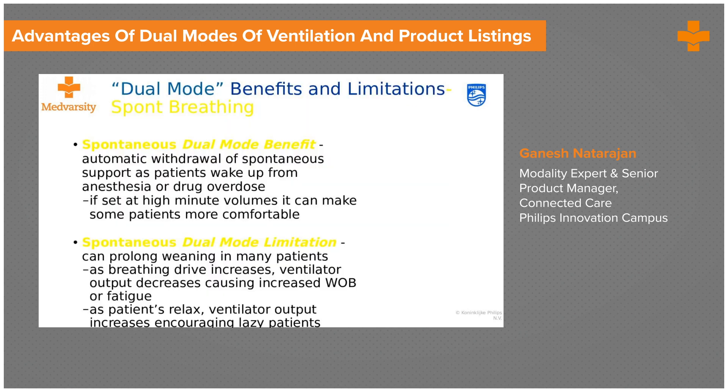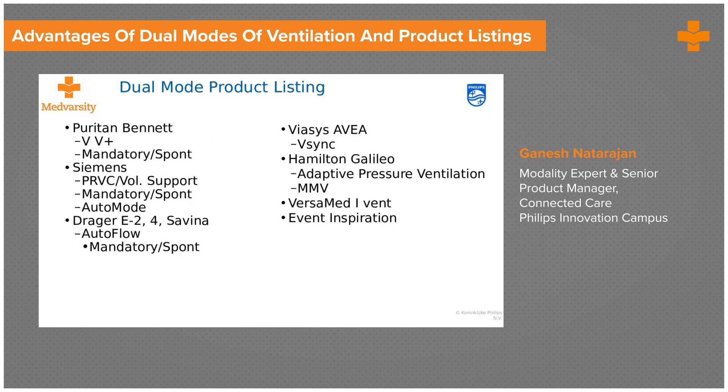These are the various names by which PRVC is known across the industry. Puritan Bennett calls it volume ventilation plus. Siemens — the company that actually came up with it — calls it PRVC. Draeger calls it autoflow. Viasys calls it V-Sync. And Hamilton calls it APV.